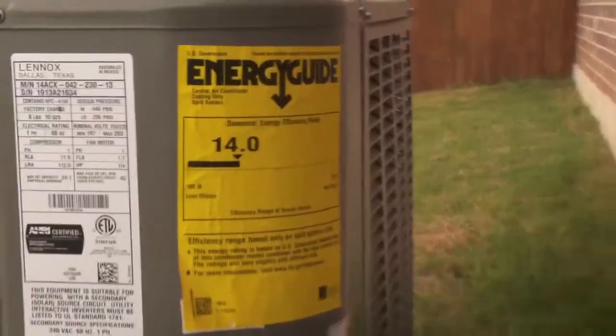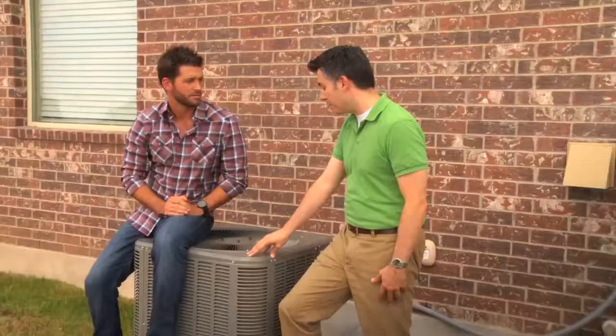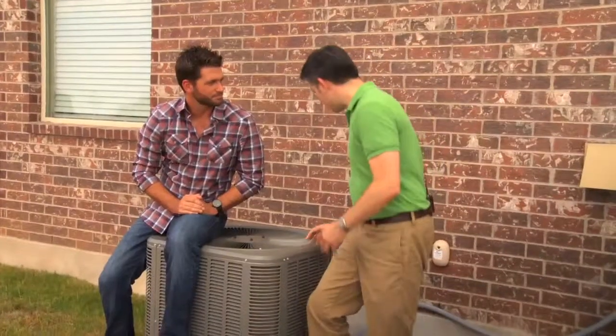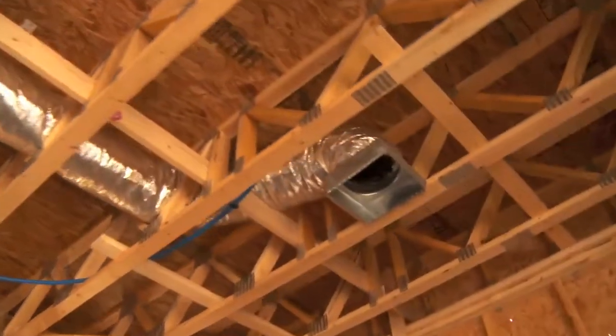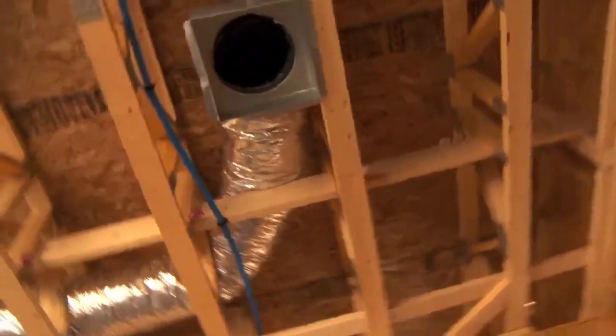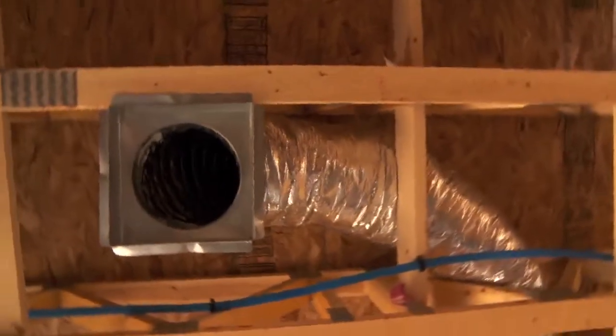I'm happy to say new homes deliver on all three fronts. Number one, having a high SEER rating, but also the size of your system really matters. On top of that, the sizing of your ductwork, as well as the seal inside that ductwork, is very important and critical.